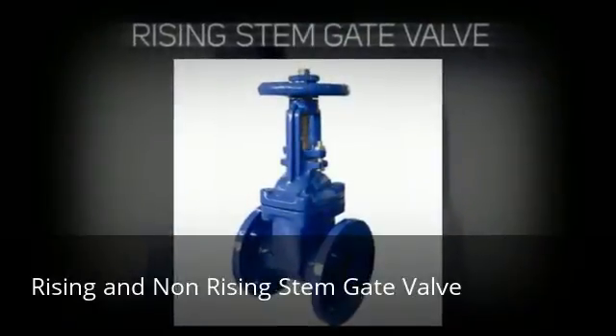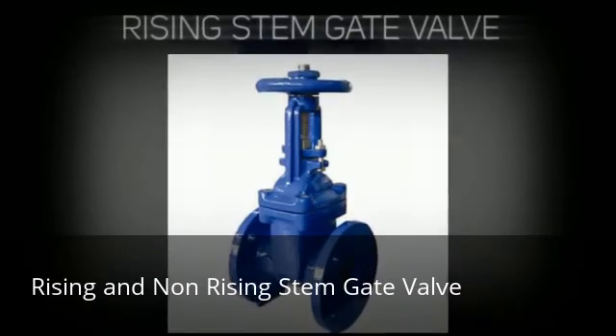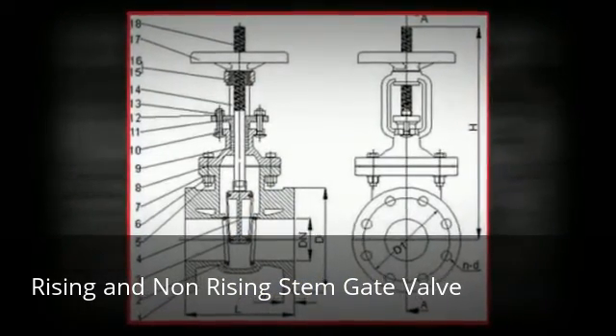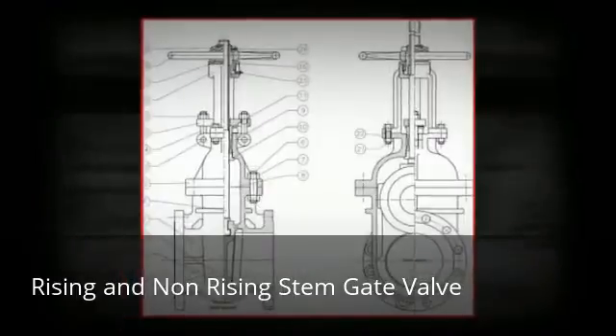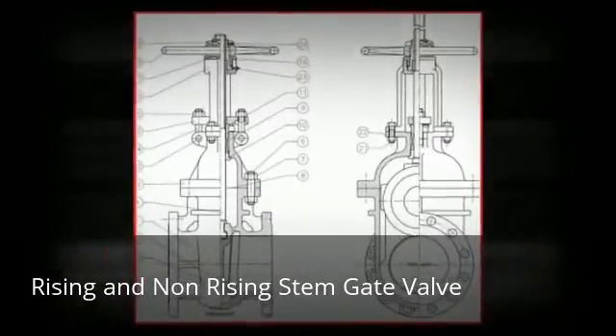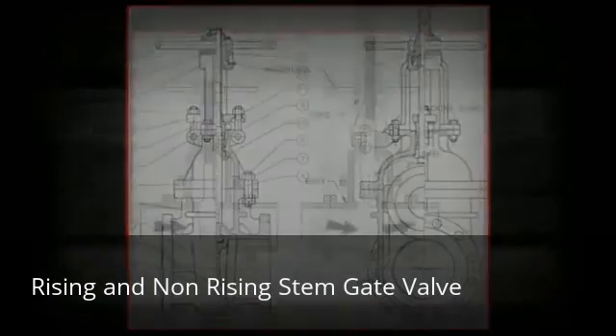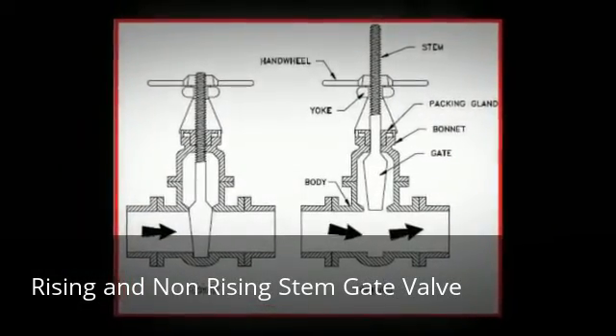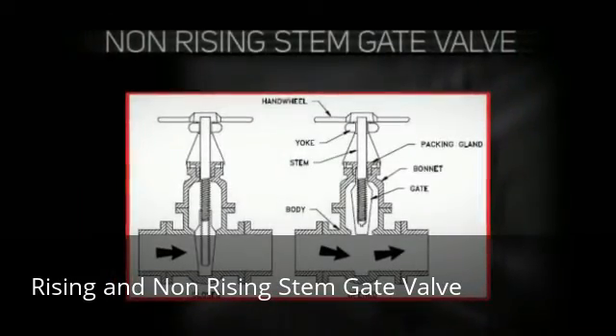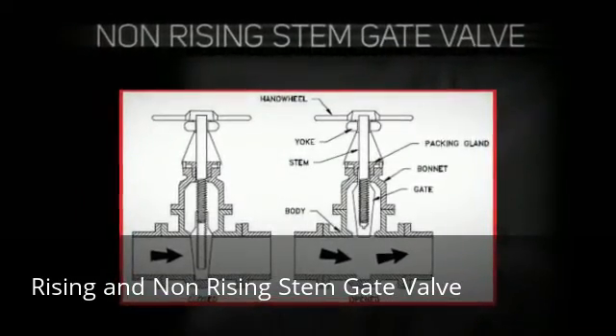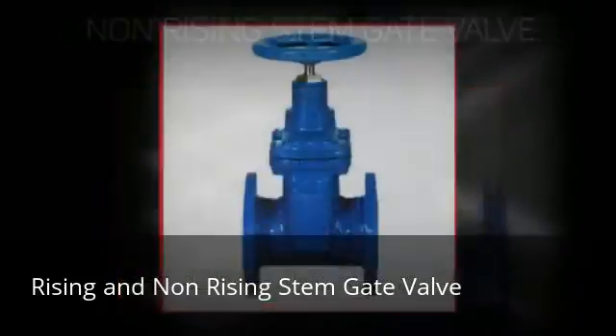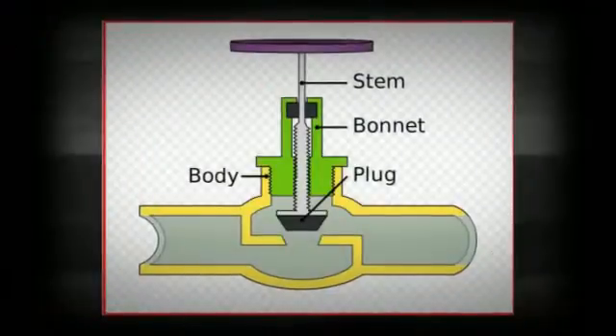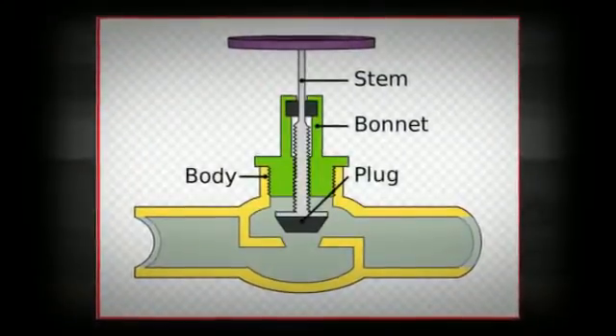Gate valves are characterized as having either a rising or non-rising stem. Rising stems provide a visual indication of valve position because the stem is attached to the gate such that the gate and stem rise and lower together as the valve is operated. Non-rising stem valves may have a pointer threaded onto the upper end of the stem to indicate valve position, since the gate travels up or down the stem on the threads without raising or lowering the stem. Non-rising stems are used underground or where bonnets provide leak-proof closure for the valve body.